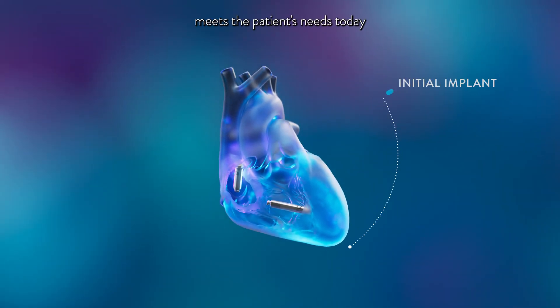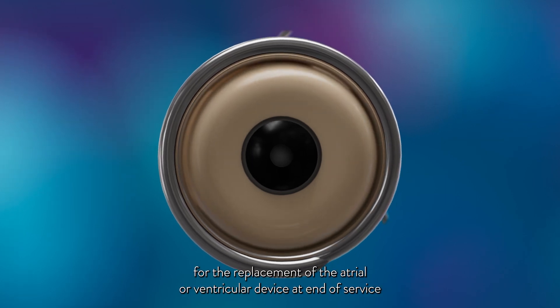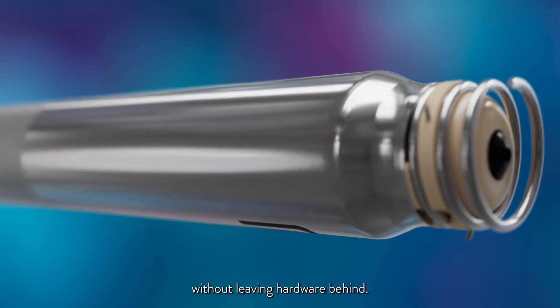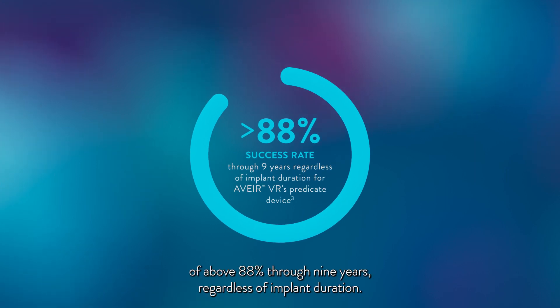The option to upgrade over time meets the patient's needs today and accommodates for disease progression tomorrow. The helical design facilitates long-term retrieval for the replacement of the atrial or ventricular device at end-of-service without leaving hardware behind. The Aveir VR's predicate device has a long-term retrieval success rate of above 88% through nine years, regardless of implant duration.